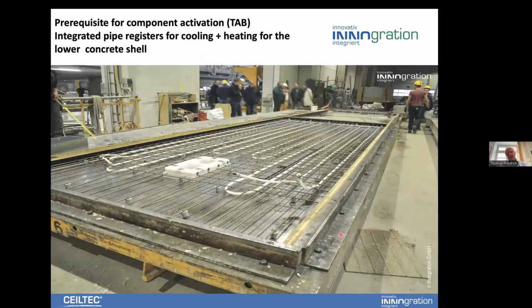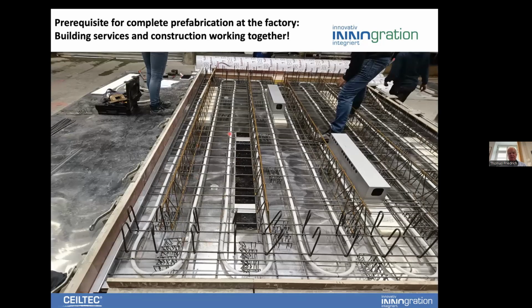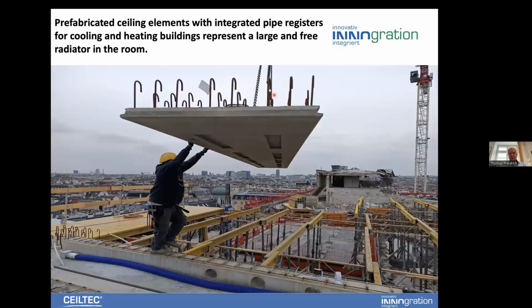As I mentioned, the cross-section can only be done with prefabrication, and you can see here that we place the tubes very precisely into the slab system, into the lower part, as shown here and in another area here. They are very precisely placed, and this precision can be done exactly in the fabrication plant. You bring them to the construction site, and as I mentioned, this gives you a huge area, about 20 square meters, free to bring energy into the room.